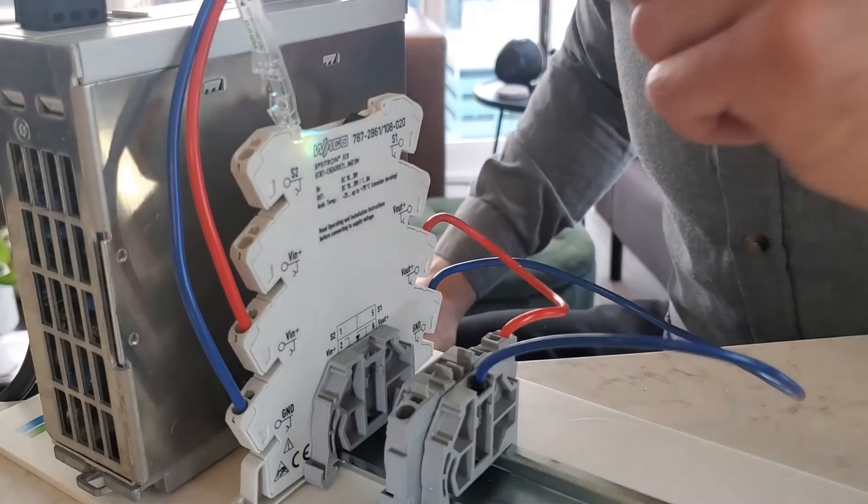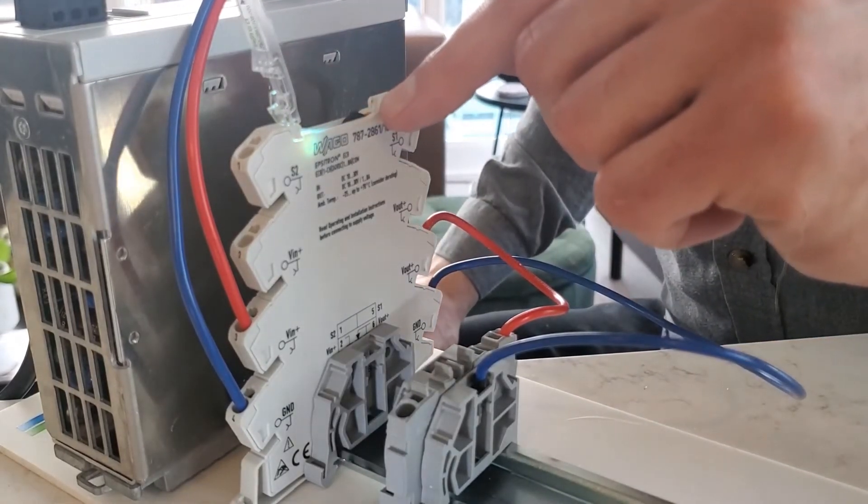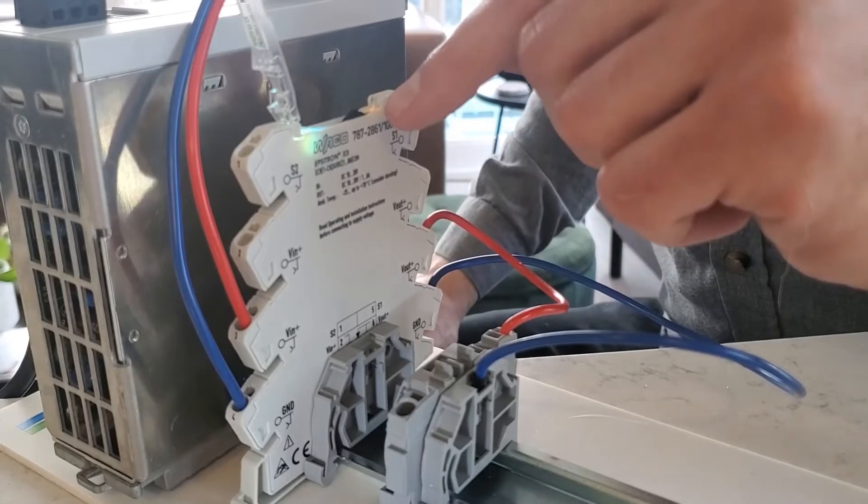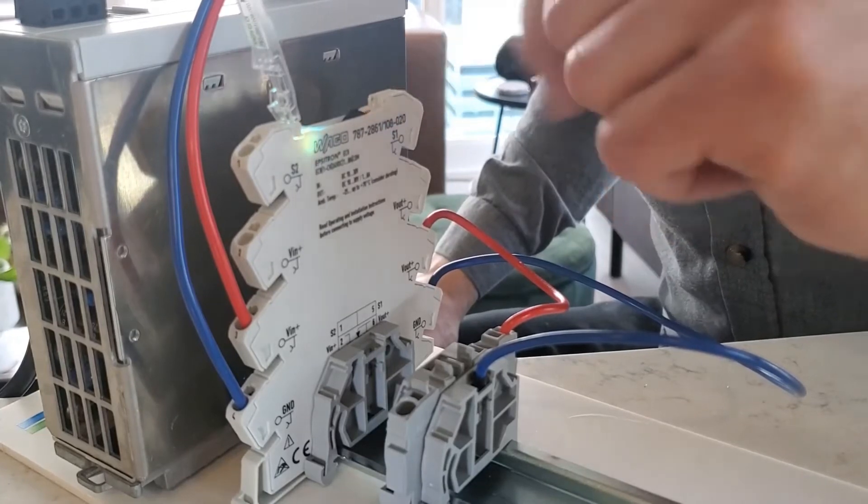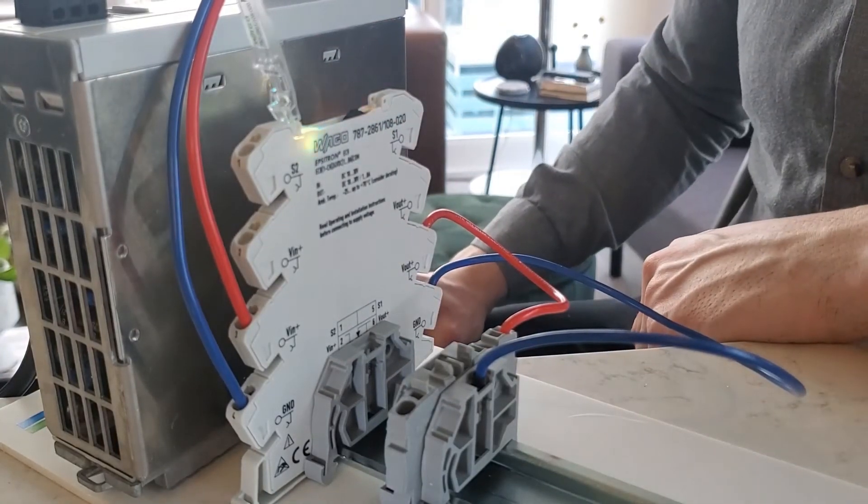If I look at this amber blinking LED, it's blinking four times with a pause, which indicates that it's set for a current level of 4 amps.